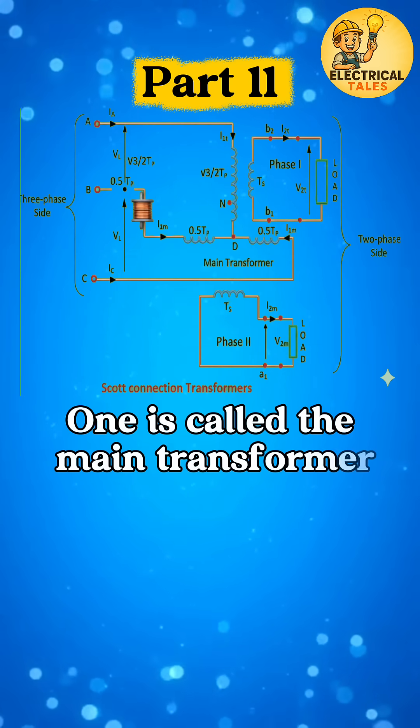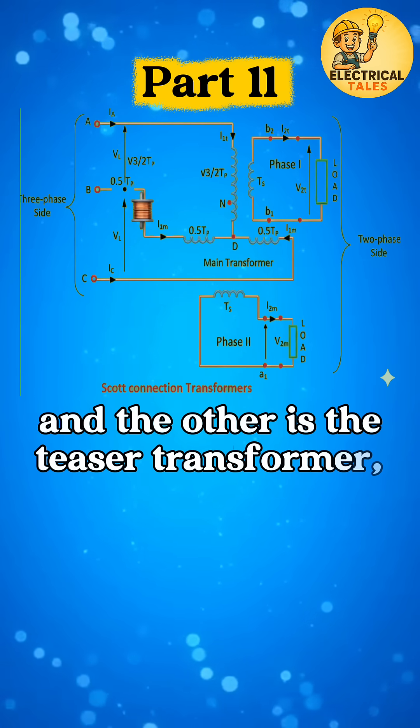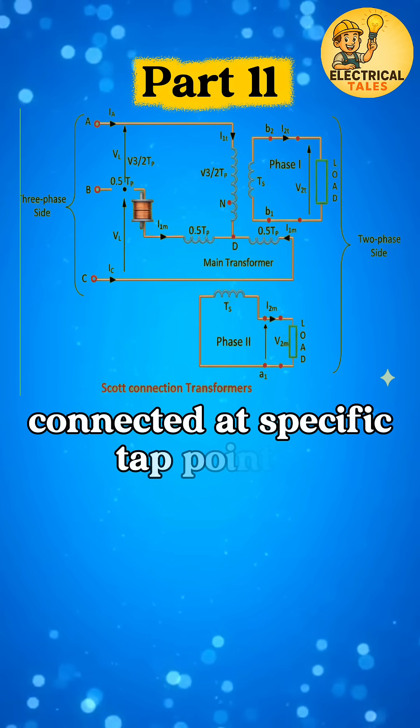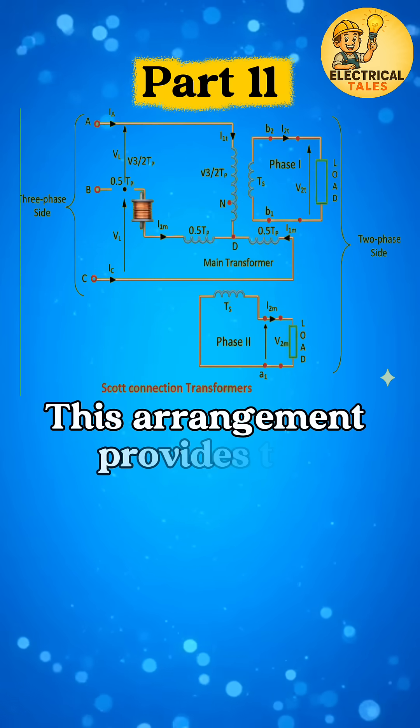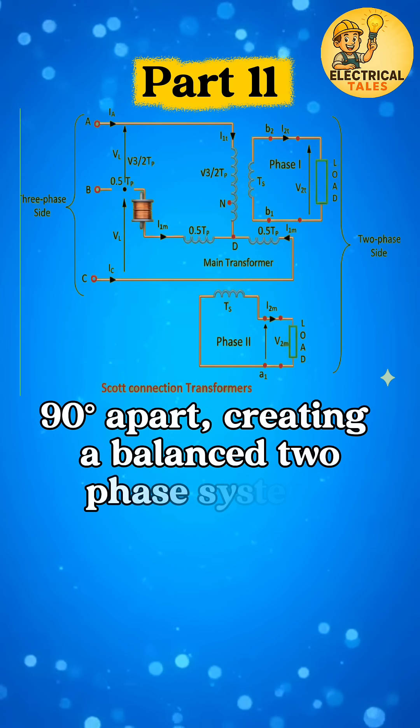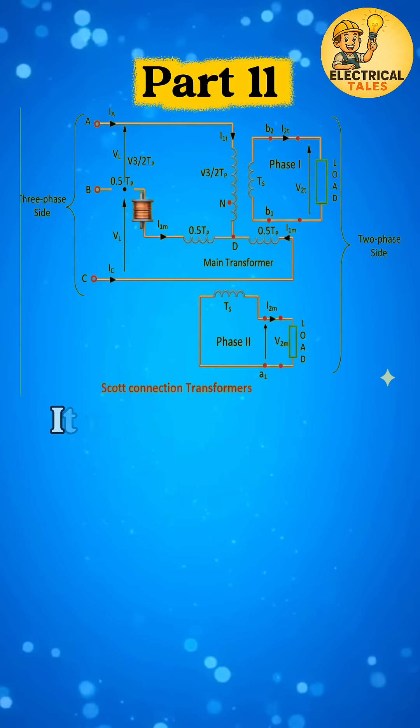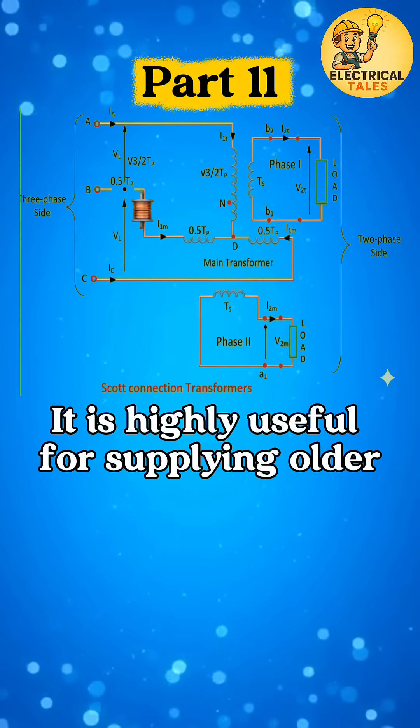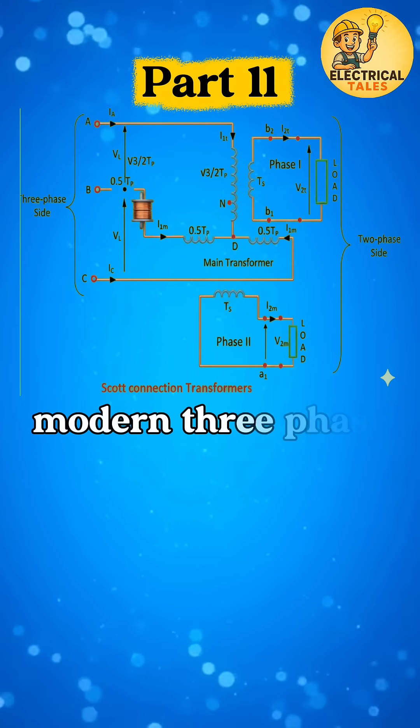One is called the main transformer and the other is the teaser transformer, connected at specific tap points. This arrangement provides two equal voltages 90 degrees apart, creating a balanced two-phase system. It is highly useful for supplying older two-phase equipment from modern three-phase networks.